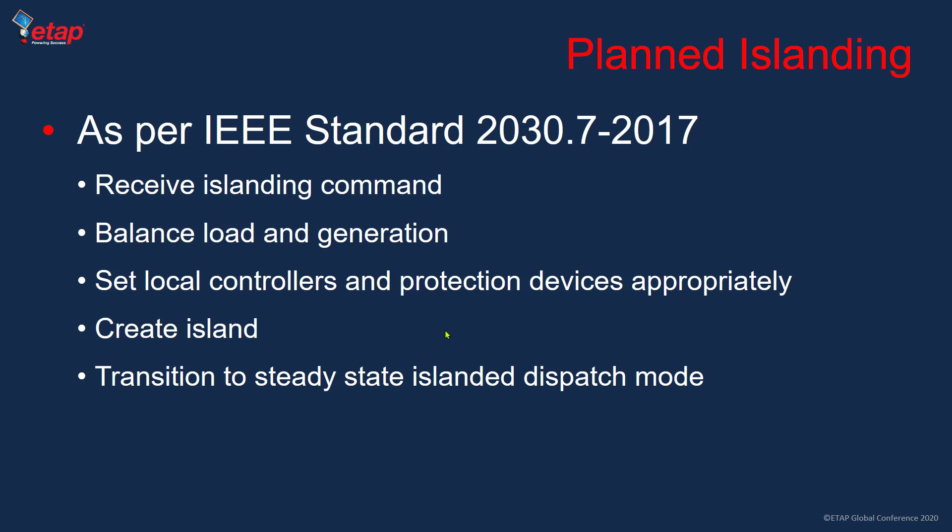A few minutes before islanding, the system balances load and generation by increasing battery discharge power to minimize import power. If needed, it starts a generator. If significant import power remains, it performs load shedding.